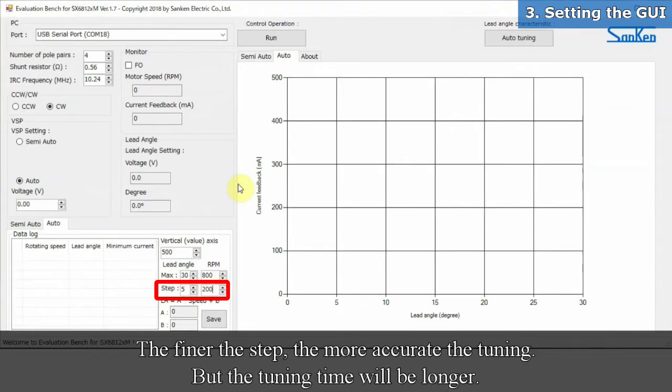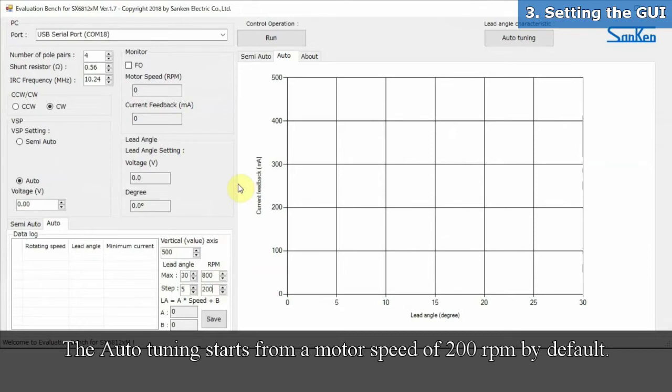The finer the step, the more accurate the tuning, but the tuning time will be longer. The auto-tuning starts from a motor speed of 200 RPM by default.